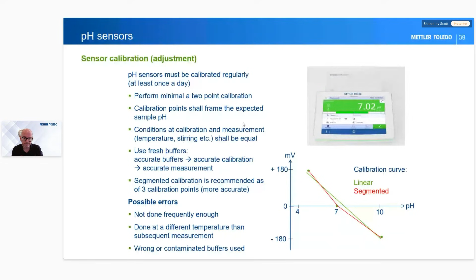We've got some more slides on buffers. When we're using buffers and buffer handling, we should make sure we look at the expiry dates. This is a picture of the Mettler bottles with an expiry date on, but you should always check the expiry dates, make sure they're in date. Once they're opened, write the date of opening on the bottle so you know how long that bottle's been open for. The other thing we do is we never calibrate inside that bottle.